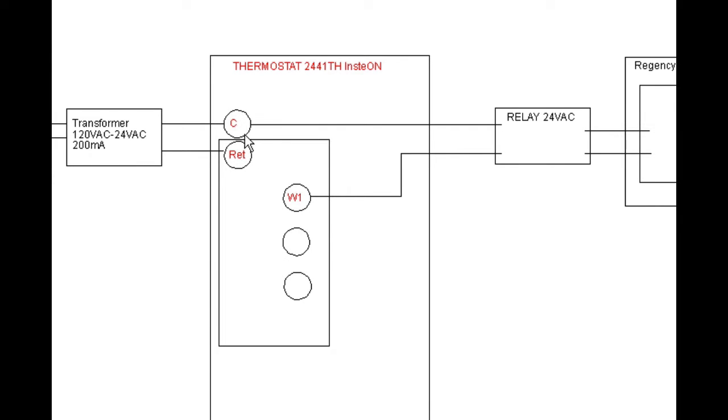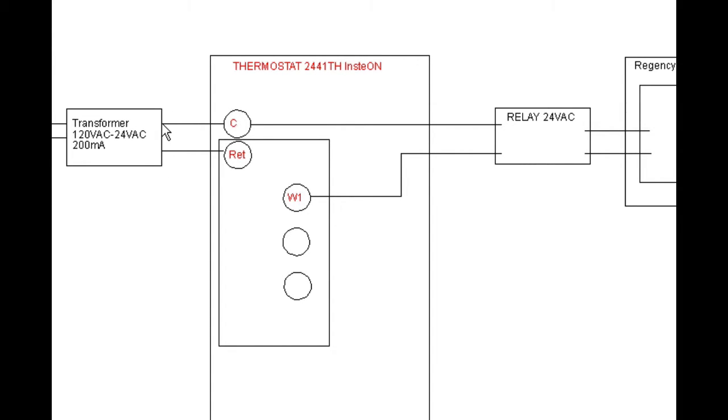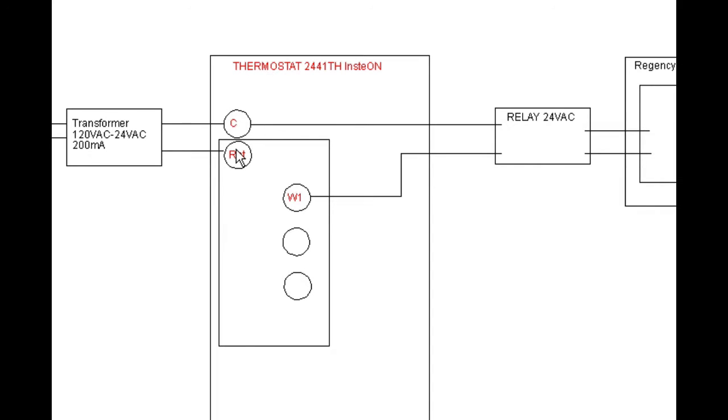So we've got a transformer, has 120 volts on this side and 24 volts all the time on this side. The 24 volts gets applied to common and return, and that's what energizes and runs the thermostat.